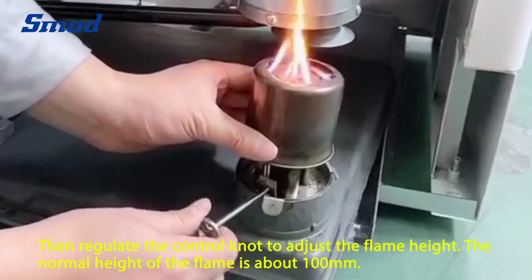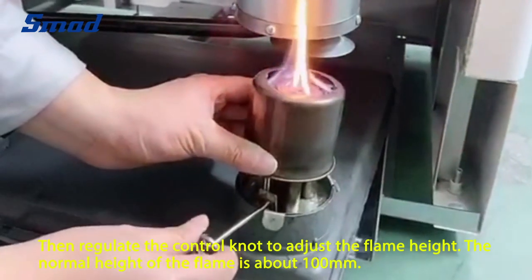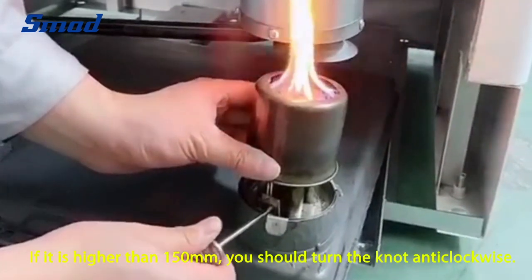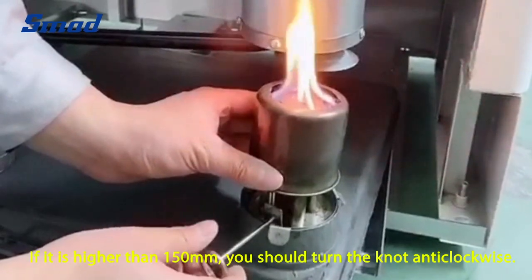Then, regulate the control nut to adjust the flame height. The normal height of the flame is about 100 mm. If it's higher than 150 mm, you should turn the knob anti-clockwise.